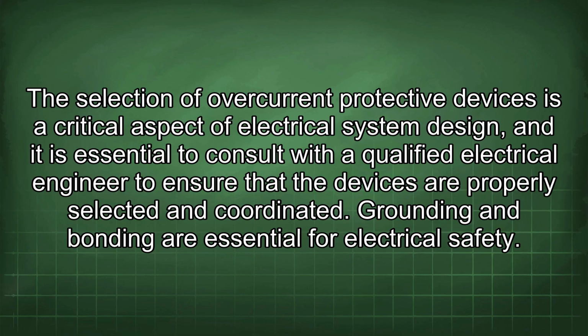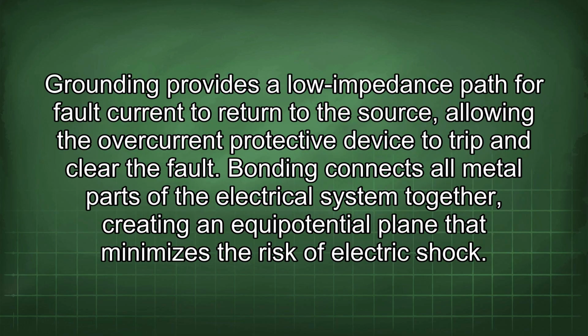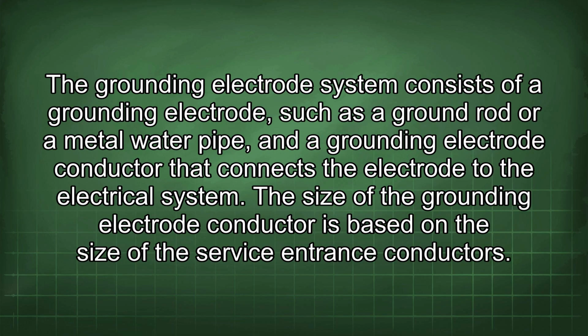Grounding and bonding are essential for electrical safety. Grounding provides a low-impedance path for fault current to return to the source, allowing the overcurrent protective device to trip and clear the fault. Bonding connects all metal parts of the electrical system together, creating an equipotential plane that minimizes the risk of electric shock. The grounding electrode system consists of a grounding electrode, such as a ground rod or a metal water pipe, and a grounding electrode conductor that connects the electrode to the electrical system. The size of the grounding electrode conductor is based on the size of the service entrance conductors.